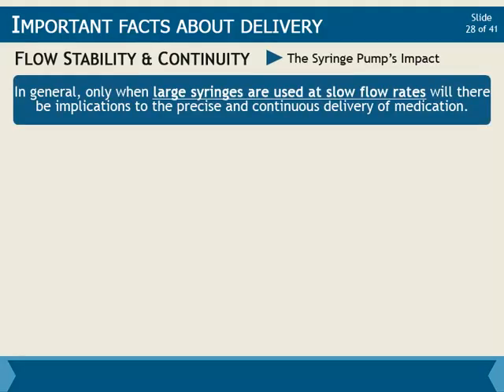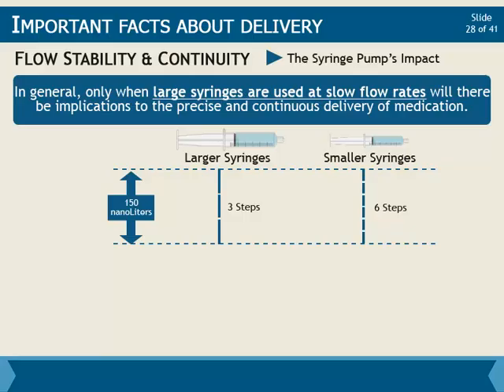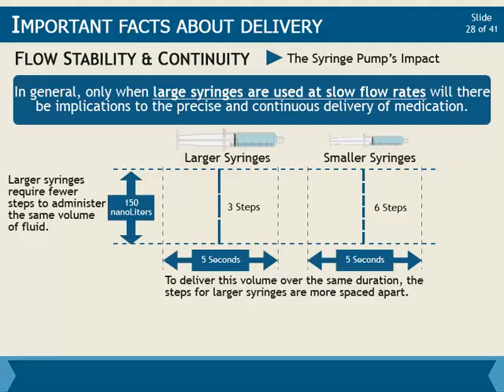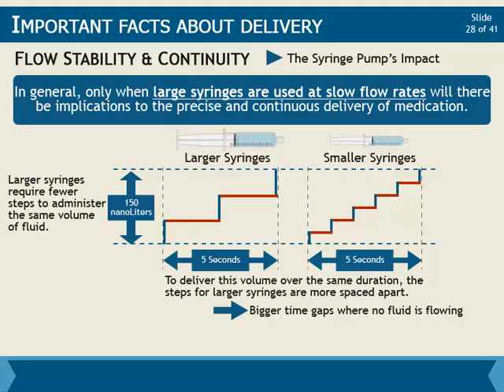In general, only when large syringes are used at slow flow rates will there be implications to the precise and continuous delivery of medication. For large syringes with a bigger diameter, each step forces a greater amount of fluid out of the syringe. This means, when compared to syringes with a smaller diameter, larger syringes require fewer steps to administer the same volume of fluid. Furthermore, in order to deliver this volume over the same duration, the steps for larger syringes are more spaced apart. Therefore, for large syringes, there are bigger time gaps where no fluid is flowing, resulting in reduced flow continuity. The larger the syringe, the more continuity is impacted.